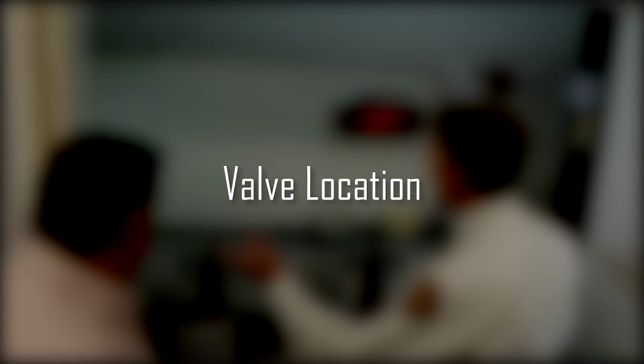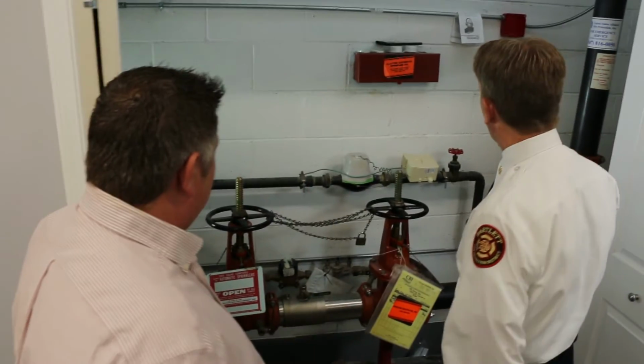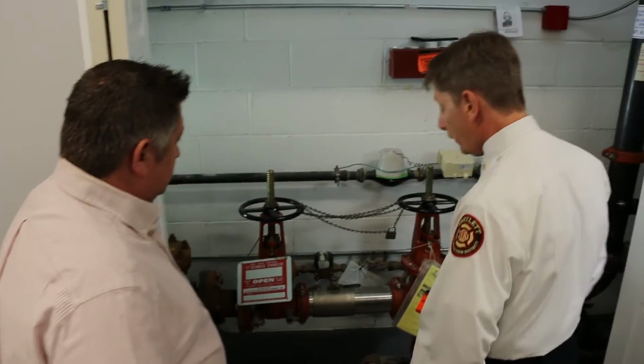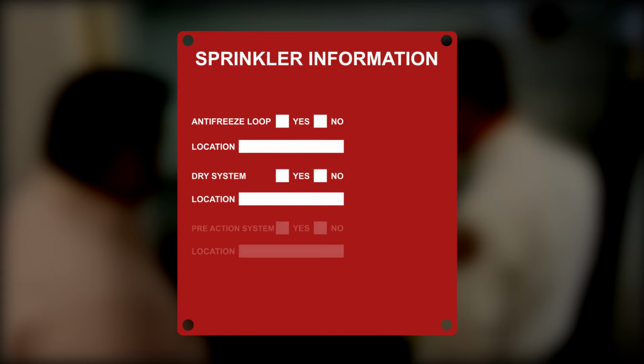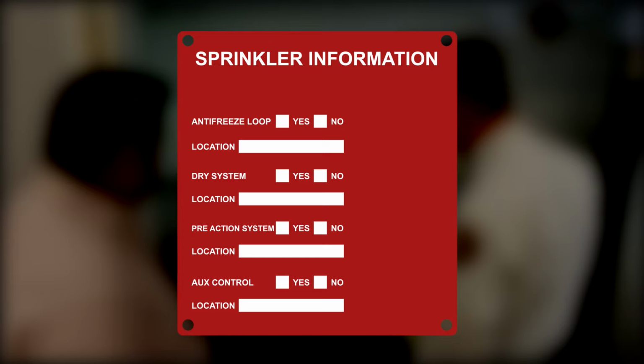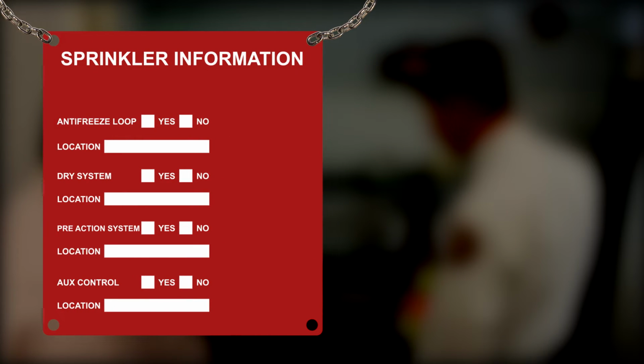Be sure to identify the location of shutoff valves at the system riser or other approved locations. At the system riser, you should place a permanently marked metal or rigid plastic information sign if it supplies an antifreeze loop, dry system, pre-action system, or auxiliary control valve. Each sign must be secured with a corrosion-resistant wire, chain, or other approved means, and must indicate at least the following information.